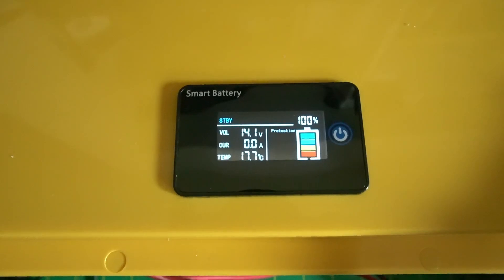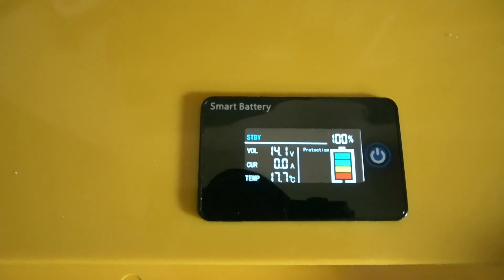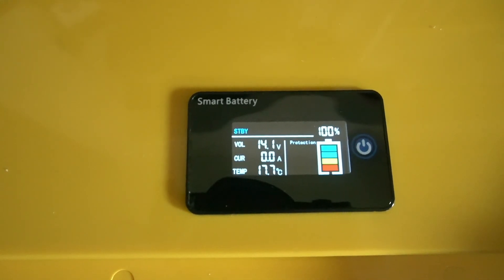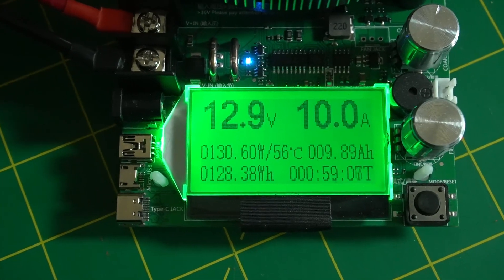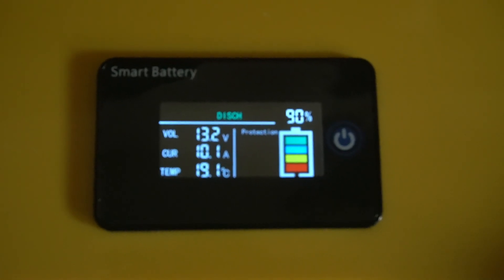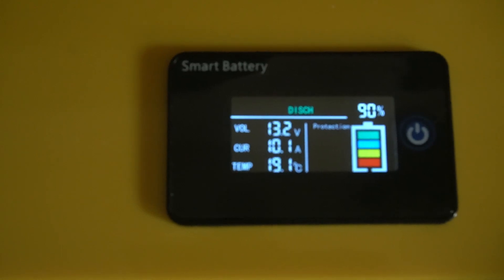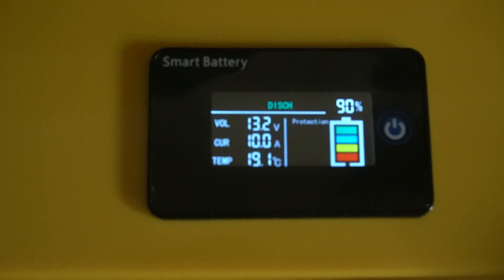The meter shows 100% — this is the meter on the battery itself. It says 14.1 volts, temperature 17.7°C, full charge, 100%. So we're at 50% — let's see how accurate that is. We're still at 12.9 volts, 10 amps, and about 9.8-9.9 amp-hours on the capacity tester. The battery meter says 90% — that's pretty close. And right here it says 10.1 amps, so it's actually showing the draw on the battery too. Fairly accurate so far.